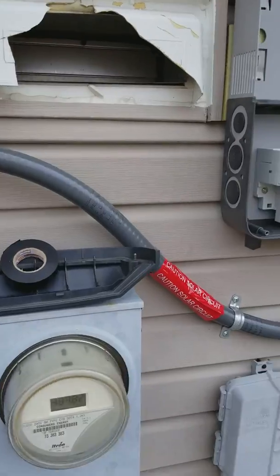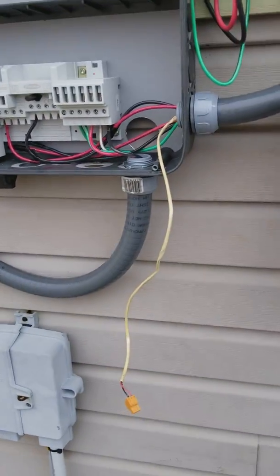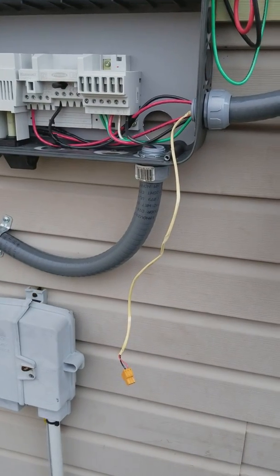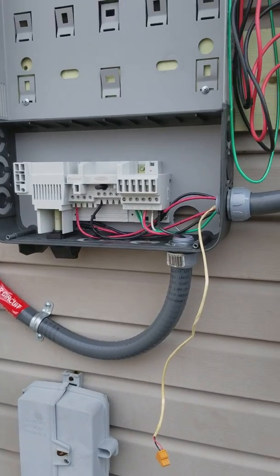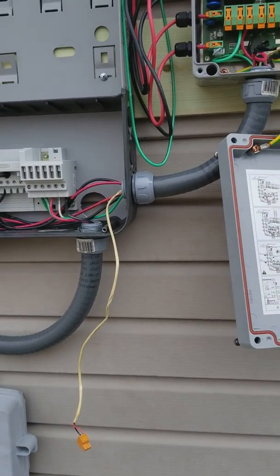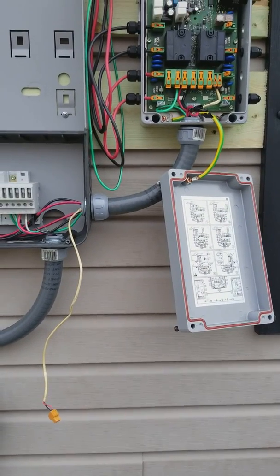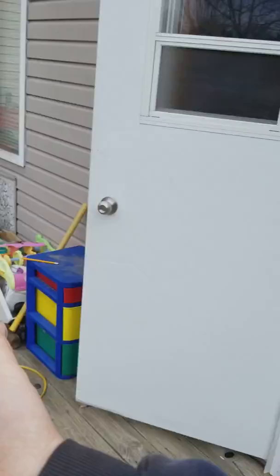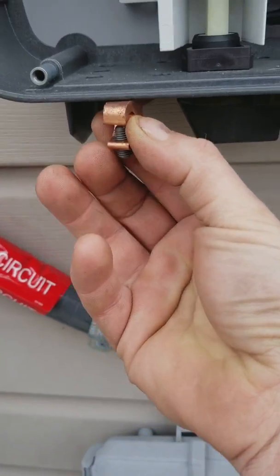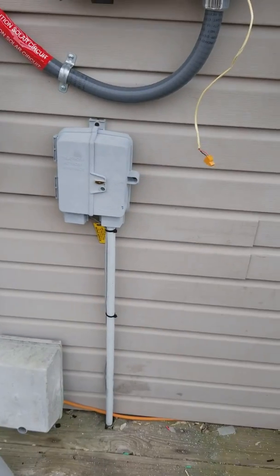For grounding you got to have number six bare — solid, not stranded. We didn't have rails; everything we made ourselves out of aluminum. They're called WEEBs — like a washer — and when you put them on your solar panels they ground to your rail. Since I didn't have those, we bought connectors and grounded each panel individually with number six. We bought those screws, screwed them onto the bottom side of the solar panel and ran the wire into it. Menards had two-packs for about a buck twenty-five. We're in Michigan, north of Grand Rapids.